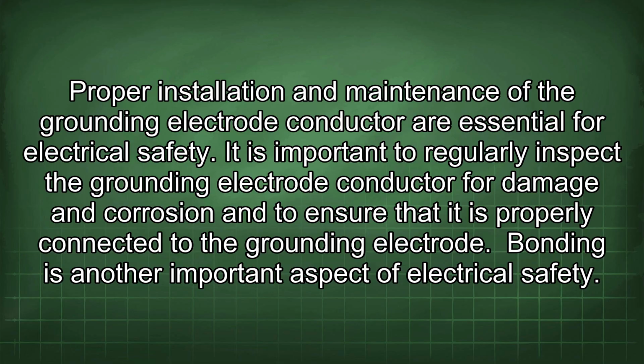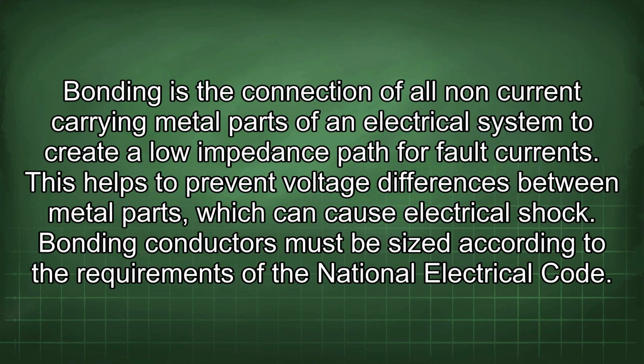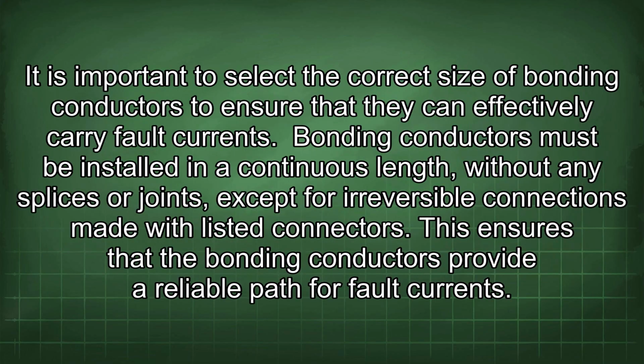Bonding is another important aspect of electrical safety. Bonding is a connection of all non-current carrying metal parts of an electrical system to create a low impedance path for fault currents. This helps to prevent voltage differences between metal parts, which can cause electrical shock. Bonding conductors must be sized according to the requirements of the National Electrical Code. It is important to select the correct size of bonding conductors to ensure that they can effectively carry fault currents.